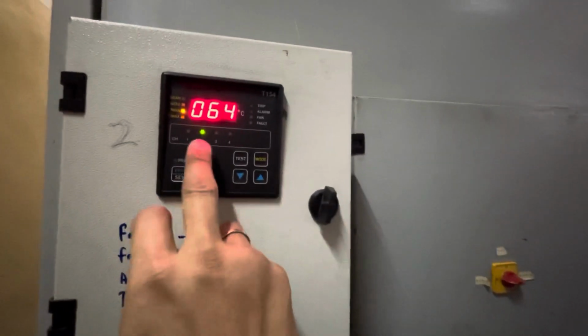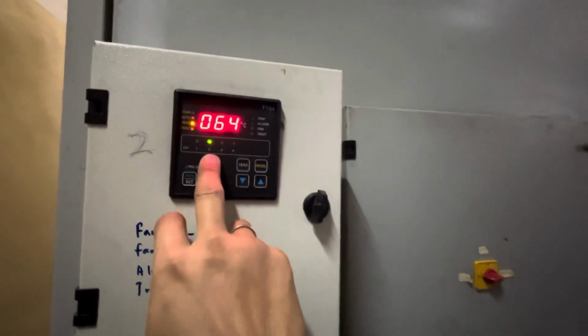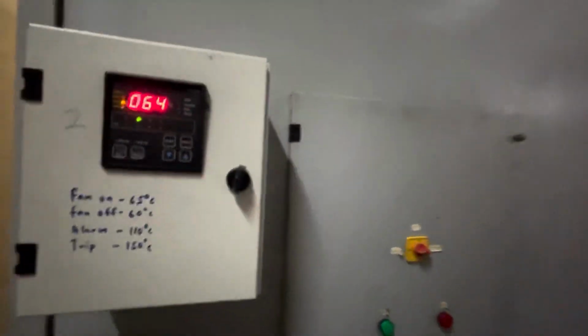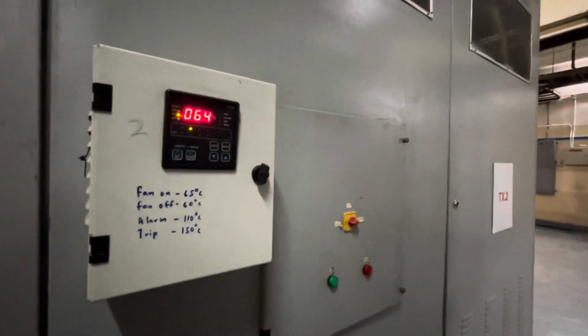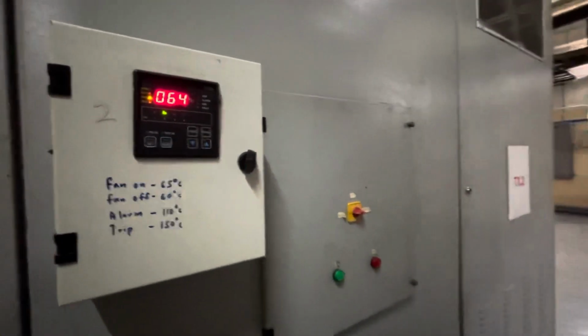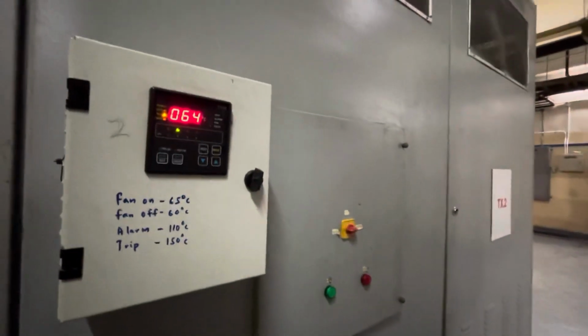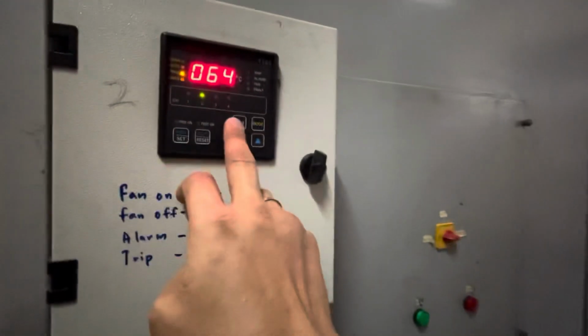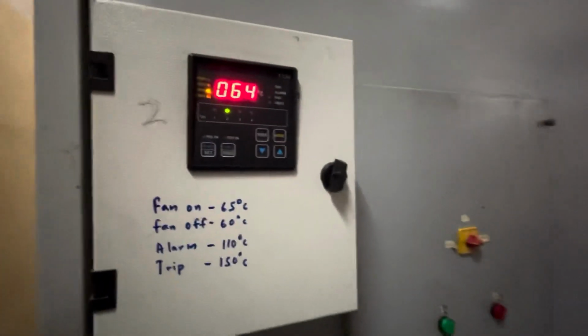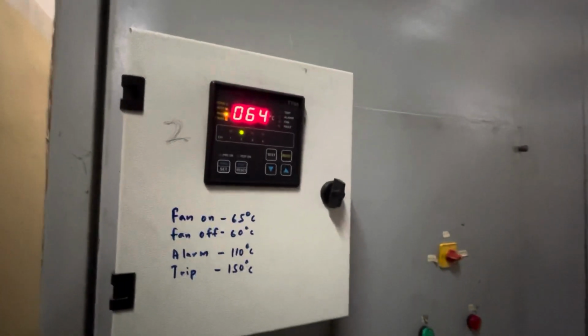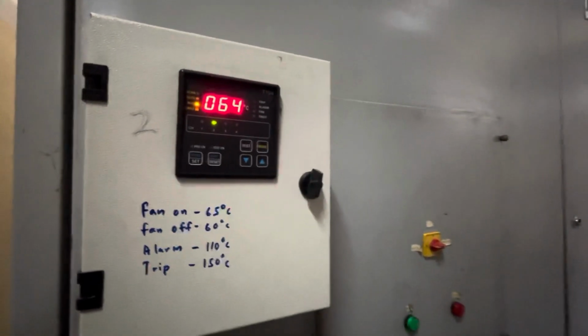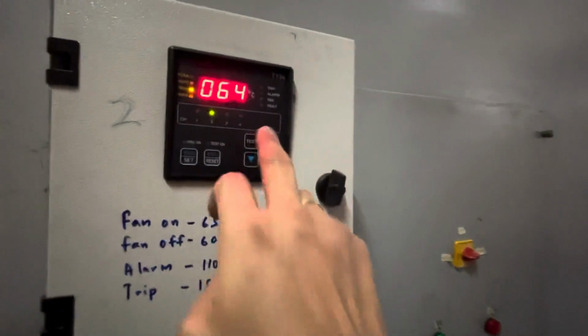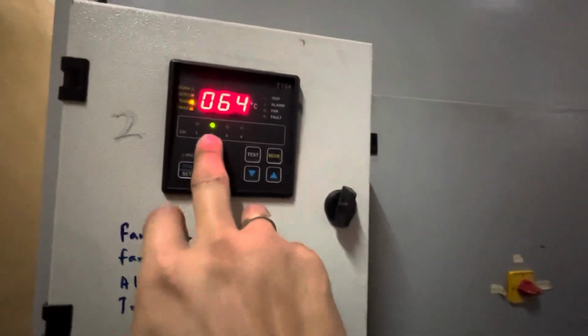Always the yellow phase will be much warmer. It's due to the middle. It's located at the middle, because normally the heat dissipation at the middle core will be much slower, because on the left hand side you have another core and on the right hand side you have another core, compared to the red and the blue. At the side of those there's an empty space, so the heat dissipation is much more effective compared to red phase and blue phase. The yellow phase has less heat dissipation, so that is why the yellow phase is always higher.